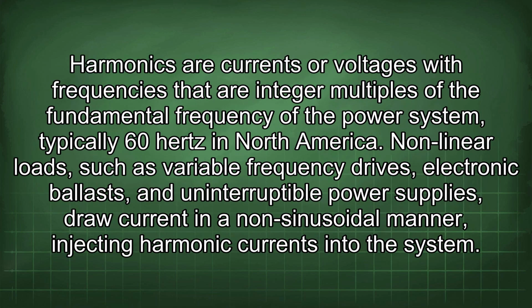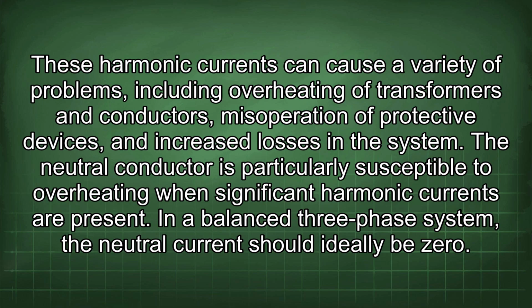Harmonics are currents or voltages with frequencies that are integer multiples of the fundamental frequency of the power system, typically 60 Hz in North America. Nonlinear loads, such as variable frequency drives, electronic ballasts, and uninterruptible power supplies, draw current in a non-sinusoidal manner, injecting harmonic currents into the system. These harmonic currents can cause a variety of problems, including overheating of transformers and conductors, misoperation of protective devices, and increased losses in the system.